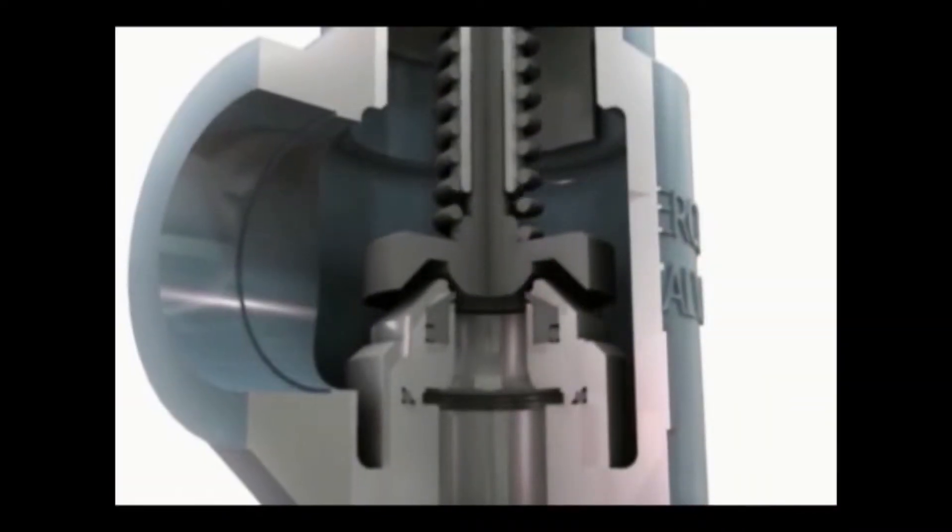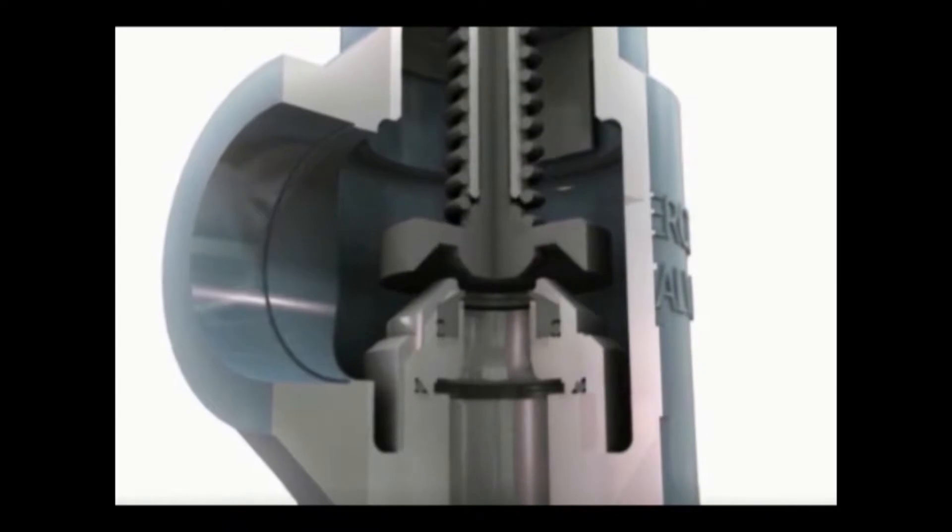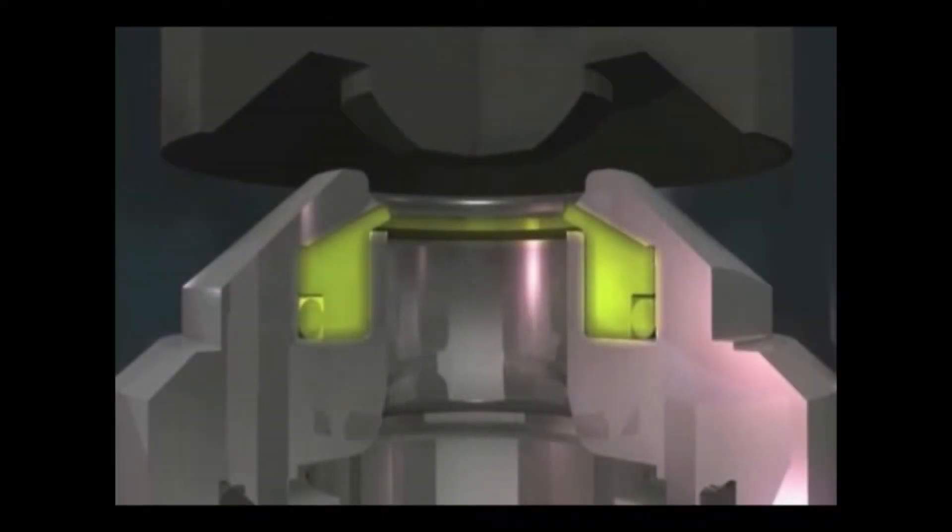The lip seal seat also does not absorb the brute impact of the disc closing. To avoid the impact, the seat flexes down as the disc closes, allowing the metal nozzle to stop the disc movement.